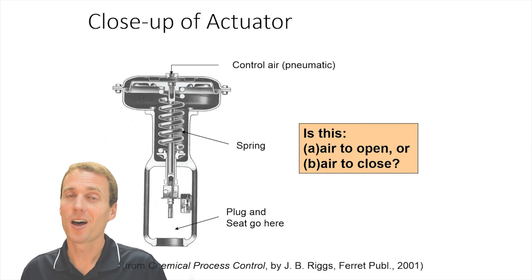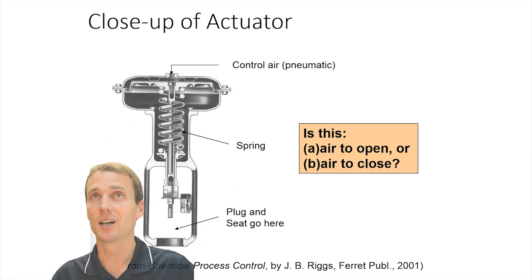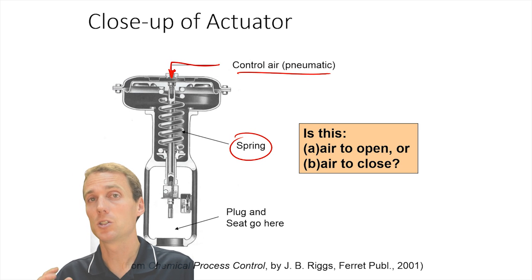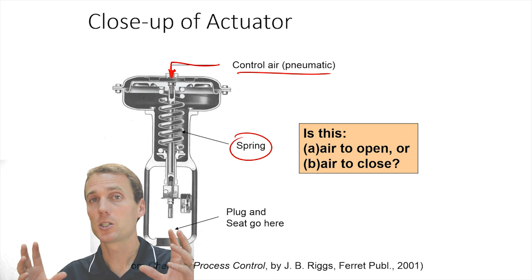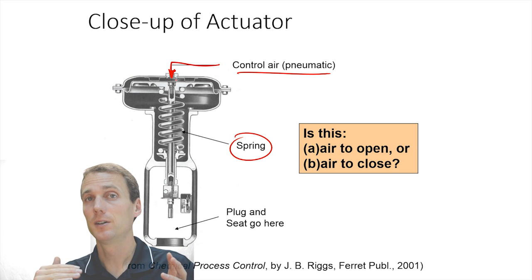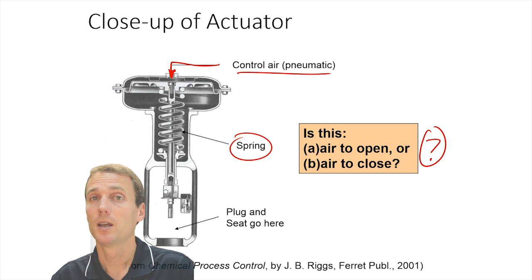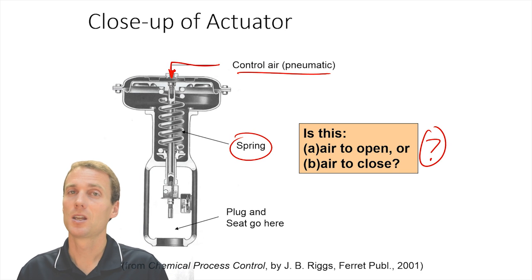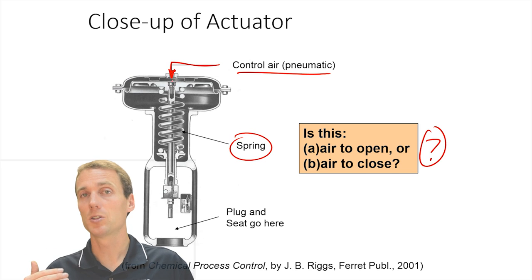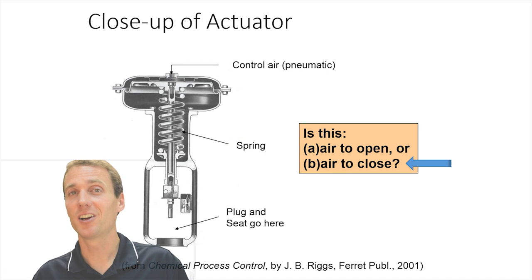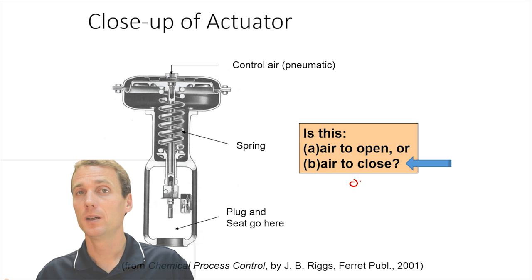Let's take a look at another one. Here is one of these diaphragms with the spring actuator. The air is coming in from the top, so as you increase the air pressure in the top, it's going to close the valve. So is this an air-to-open or air-to-close valve? If I apply air pressure, does it open the valve or close the valve? And is it going to fail open or fail closed? This one is an air-to-close or fail-open type valve.